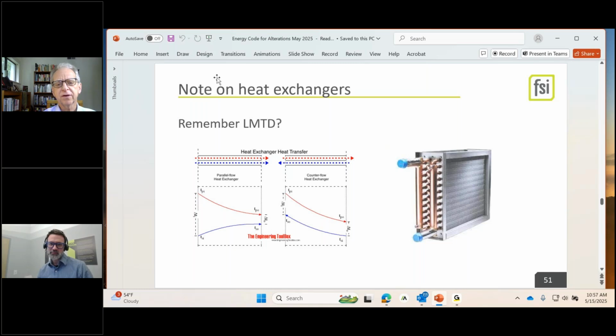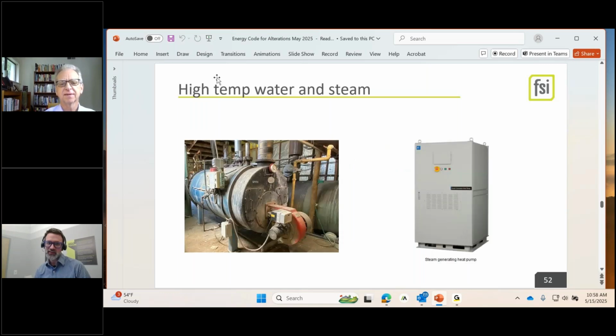I wanted to ask, I've had sales reps coming in lately with some brand spanking new thing that they say they have heat pumps that can boost water temperatures up to 170 or something. Is that real yet? Do you know? Or is that still imaginary? It is, but it often has an operational envelope that it can do that down to 30 degrees, 35, and then it starts dropping off as it loses capacity. So yes, it can, and no, it's not really effective for Seattle, and certainly not effective for east of the mountains. So when you actually need the 170-degree water, you can't get it. Exactly. Yeah, it's a fine print detail.